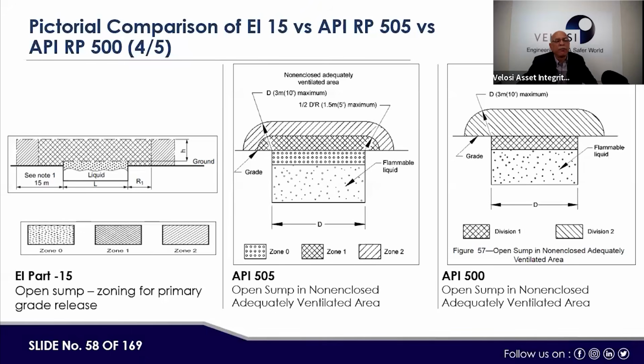Now, next, one more example, an open sump, like a drain collection sump, and how the hazardous area classification is done. For the open sump, if you see here, where the liquid is available is zone 0. Then above this height, zone 1, and then this side up to 15 meter, if you consider that note, the open sump zoning for primary release, this one is zone 1. Similarly, zone 0, zone 1, and zone 2. And here it is division 1, and then this is division 1 again, and then division 2. This is division 1 and division 2, and this one is also shown as division 1.